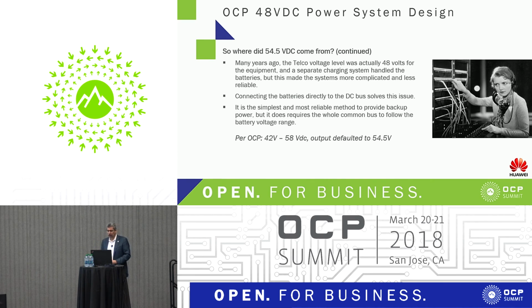The OCP recognizes that. They're not trying to tell you to use one battery or another. The range they ask the equipment to handle is 42 to 58 volts, because someone may use the OCP standard to develop a rack system with batteries that are lead acid, charging off the same bus, so the equipment has to live in this environment.